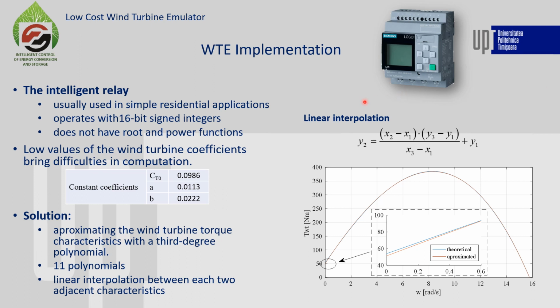Now, what are the problems? First of all, this relay operates with 16-bit signed integers and does not have root and power functions. In addition, because of the very low value of the wind turbine coefficient, and given the fact that we operate with 16-bit integers, it's very difficult to implement the mathematical expression of the wind turbine power, because the obtained results for some of the iterations are completely out of range and unacceptable.